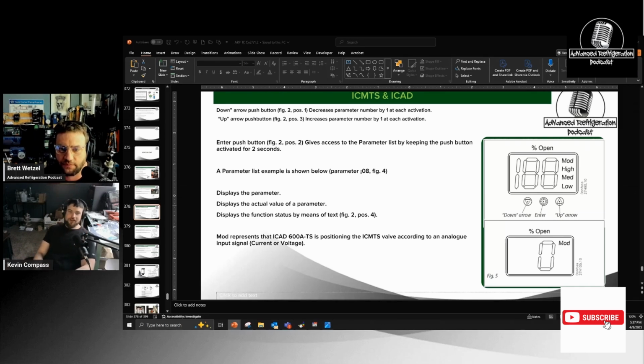No, so you've got to watch the resistance on there. So for 0 to 5, it's 250, I believe, correct? And then for 0 to 10, it's 500, or it's backwards. I always have to look it up. I'm going to have to look it up because I don't remember. One resistor makes it 0 to 5 and the other makes it 0 to 10. That is how you convert it.